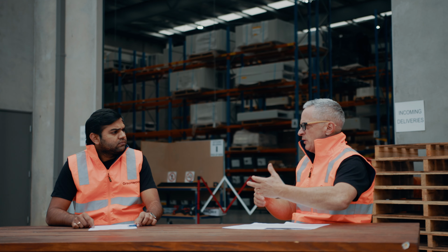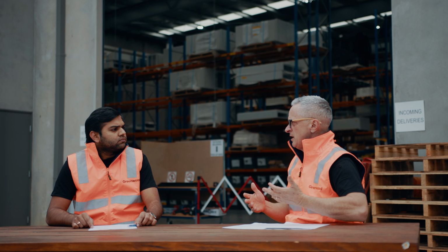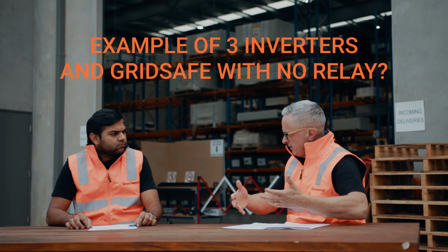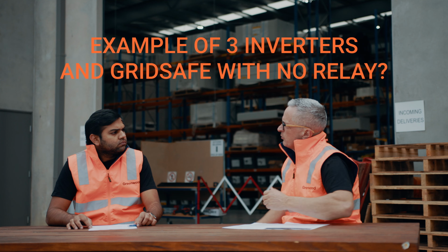Can you give me an example of a sub 200 kVA project that incorporates 3 inverters, uses a GridSafe that doesn't have a relay? We still have the network protection boards for those projects. So what would happen is one of the 110 kVA inverters would be used for the STC purpose, whereas the other 2 inverters, let's say 50 kVA and 30 kVA inverters, they would be monitored through an LGC meter for the LGC purpose. So they would have the CTs installed across those inverter breakers only.